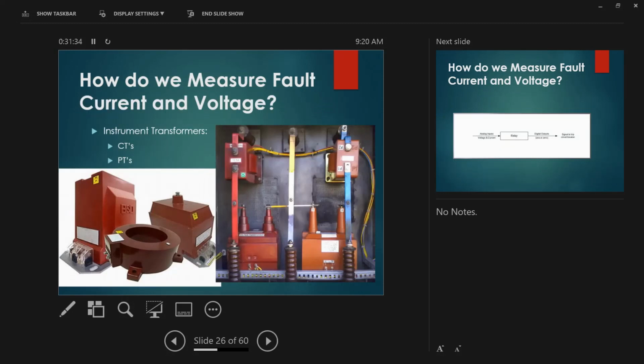Now, how do we measure the fault? That's where this comes from. Some people ignore that, saying it's only CT, don't worry about it, it's only VT. But the test result of your CT VT will be very, very important to how the relay works, or how the relay does its job. The accuracy of your CT VT and also the connection matter. Even if you have a good CT and you restore it in a wrong way, or you forgot to put the common, you forgot to open those CT links, it doesn't work. So we have to be responsible in everything that we get involved in.